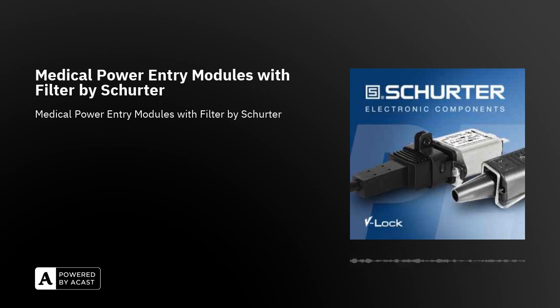Today we will be talking about medical power entry modules with filter by Schurter. Power entry modules, otherwise known as PEM, with a filter must comply with the basic standard for medical electrical equipment, IEC UL 60601-1. Let's see how Schurter PEMs meet these requirements.